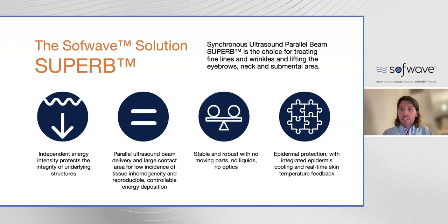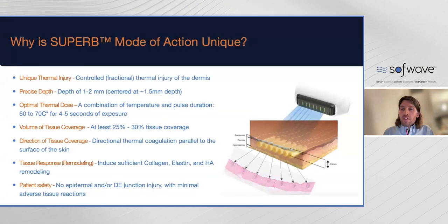We'll take a closer look at the handpiece. So it's a very quick treatment. And again, it has this integrated cooling mechanism so that you protect the epidermis during the treatment, which is integral. It really provides a safe treatment and results in no downtime for the patient. So on the right, we have a figure of the handpiece, and there's 7 cylindrical transducers that emit the ultrasound energy concurrently all together, and they target a precise depth at 1.5 millimeters under the skin. So again, the epidermis is completely spared and cooled. You get this deep heating, and it really has been proven to be the optimal thermal dose of a pulse duration of about 4 to 5 seconds, where you're heating that subcutaneous or mid-dermal tissue up to about 60 to 70 degrees centigrade.